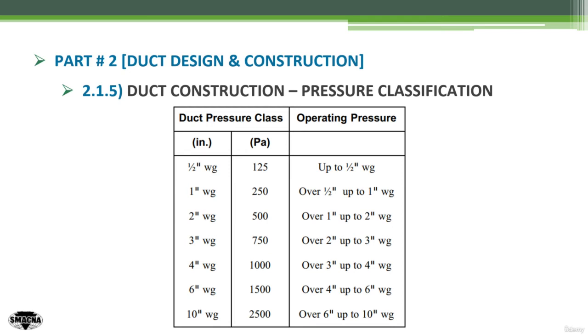For example, if I have a fan with an external static pressure of 1.5-inch water gauge, I will go to the third row as my input, which is over one inch up to two inch water gauge. This will result in an overall duct pressure classification of two inch, or 500 Pascal.